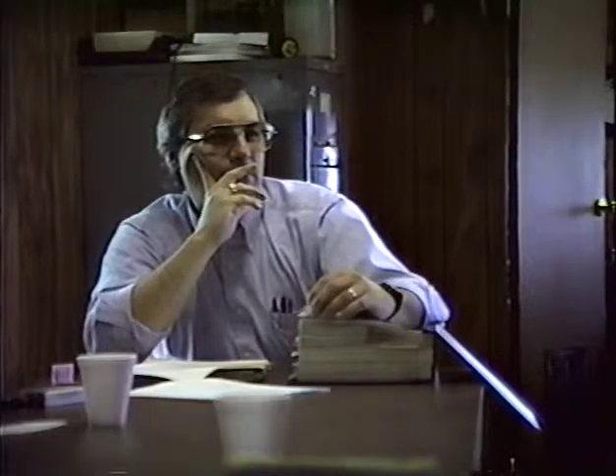Right, what Joe's really wanting, and I think I know why, is for the light to stay on the alarm panel. When it's flashing, you send the signal over to the pusher, and when it's not flashing, you ignore it as far as the pusher is concerned. I understand what you're saying, and I don't think it's that possible to do. I don't know if it's possible or not. Again, my understanding is that the intent was for someone to come over, address the alarm, determine what it is, write it down on a piece of paper, clear it, and then go address the alarm, be it a temperature, be it a pressure drop.